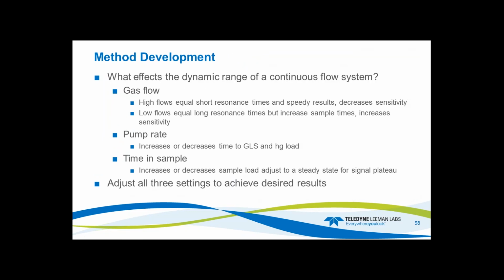So that's method development. So what affects dynamic range? In a continuous flow system like this, it is gas flow. So high flows, short residence times within the sample cell, and that will give you speedy results, but it decreases sensitivity. You decrease the gas flow, your sample times become longer, but then it also increases the sensitivity. So if you increase the sensitivity, you're lowering your instrument detection limit, your method detection limit, and so forth. Pump rate also will increase or decrease the time to the GLS. So that helps you with your throughput, and it will also increase or decrease the mercury load into the system.